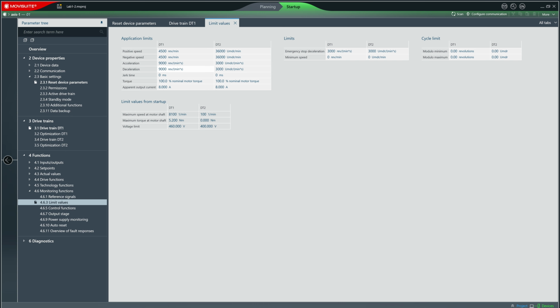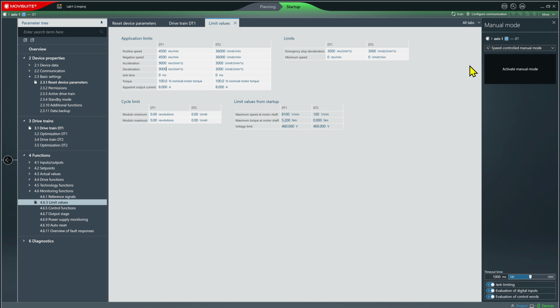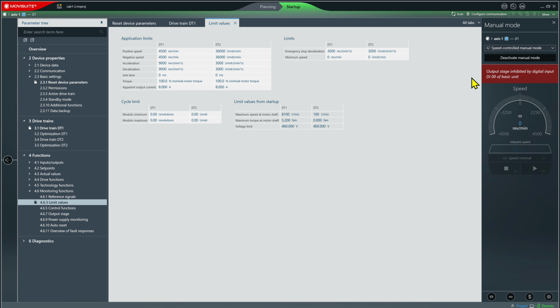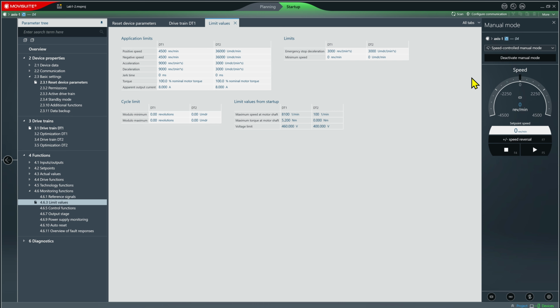Now I need to go ahead and do some basic testing to see if the motor runs. So I'm going to fire up manual mode by going to the More menu, picking the Tools menu here, picking Manual Mode. There's my manual mode tool that's just opened up. Now I need to activate it, so I click Activate Manual Mode. And notice it says the output stage is inhibited because DI00 is off. Okay, it's now time to turn that switch on. So I go to my control box and I flip DI00 on. As you can see, that removes the inhibit, and I can now run my drive.